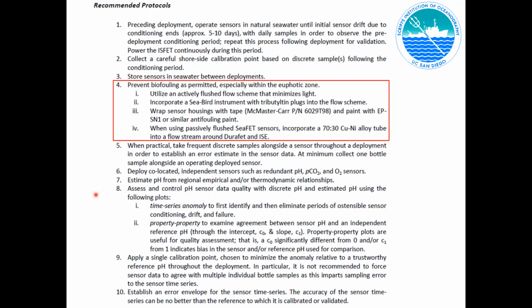So these are some of the things that we recommend, using a flushed flow scheme. This is really the progression from the SeaFET to the SeaFOX. One of the things that we decided to do is, instead of using passively flushed copper screens, use a flushed flow cell. And incorporated into that flow stream is a Seabird instrument, which is number 2 here under the 4th recommendation. Seabird CTDs are typically equipped with a tributyl tin biocide plug, and by adding that into the flow stream of your other sensors, you can really cut down on biofouling.